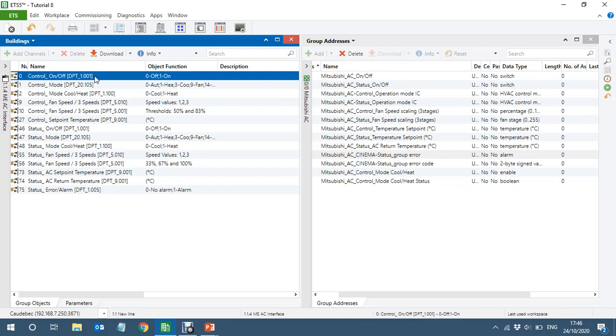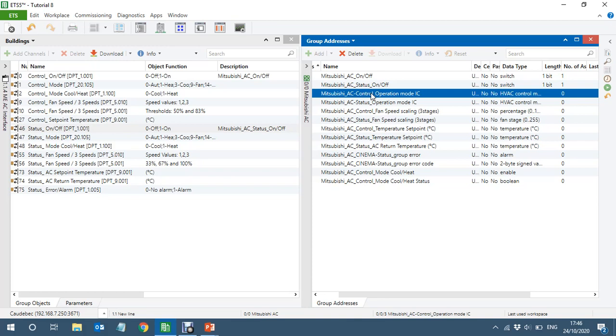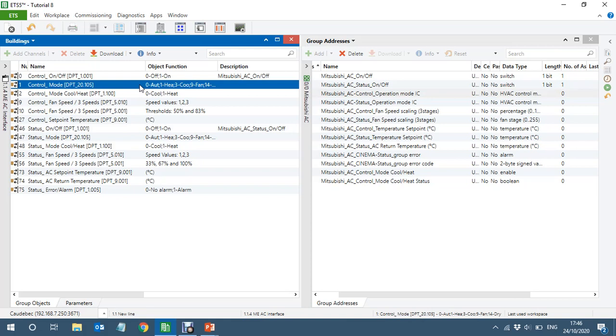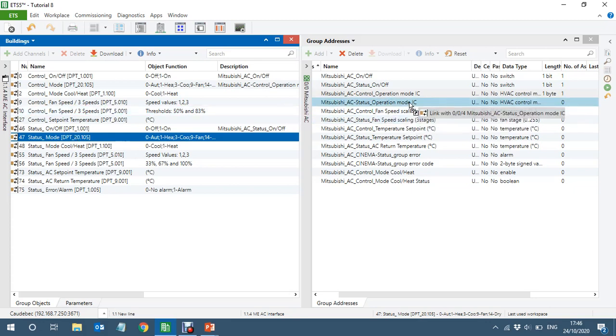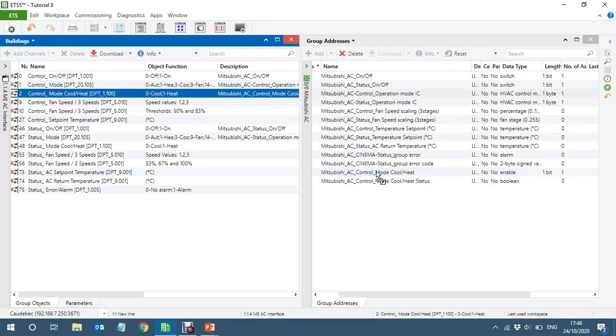The AC on/off object will turn on the Mitsubishi AC, and the status object tells us whether the AC is on or off. The operating mode — which controls auto, heat, cool, fan, or dry modes — I will link it but not control it from the RTC. Instead, I'll use the simpler heat/cool object: sending zero sets cooling mode and one sets heat mode.